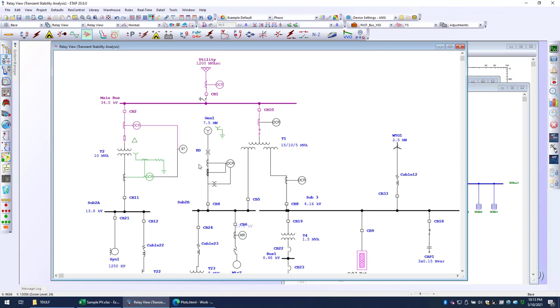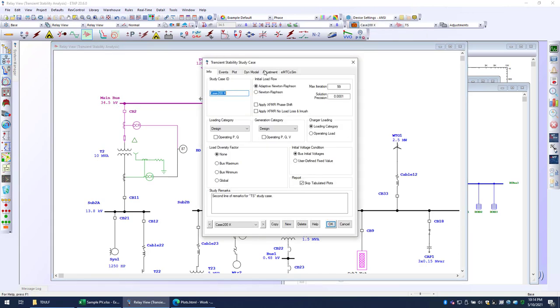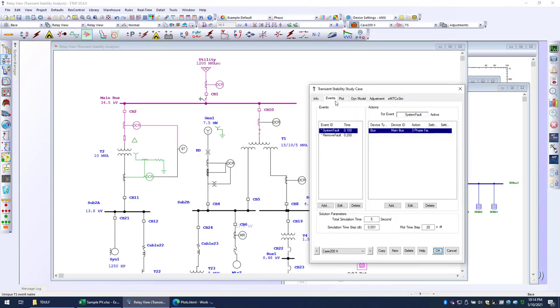And I'd like to show you how to perform two different disturbances. The first one is we're going to apply a fault here at the main bus, and then within 100 milliseconds, the recloser up here is going to clear it. So let me show you how the events are going to play for this.